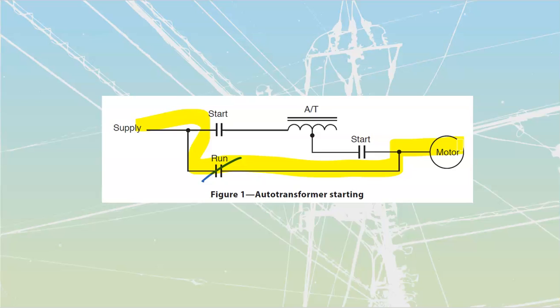And we do end up having more starting torque per line amp of current than any other type of reduced voltage starter. What they mean by that is that the line current that I'm going to have on the upstream side, because I am reducing it to come out to my actual motor during the startup, is going to be a smaller value than what the motor is going to see, but it's not all delivered. It's coming through from a high to a low, which means that ultimately I'm seeing less current coming through. Watts are still going to be the same, but I'm going to get more starting torque out of it per line amp coming in. They do have another name, compensator starters, although we don't hear it used as often as just autotransformer starters.